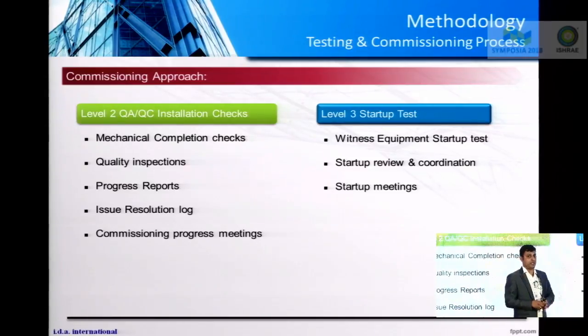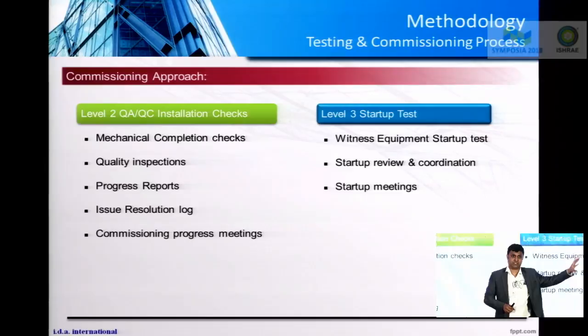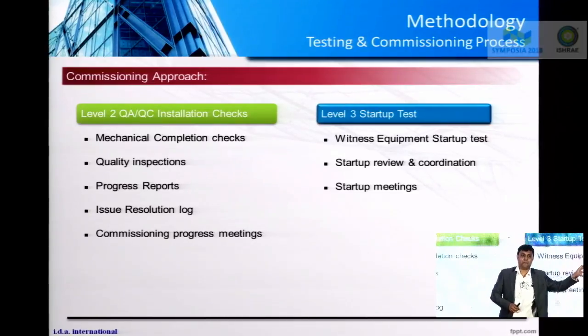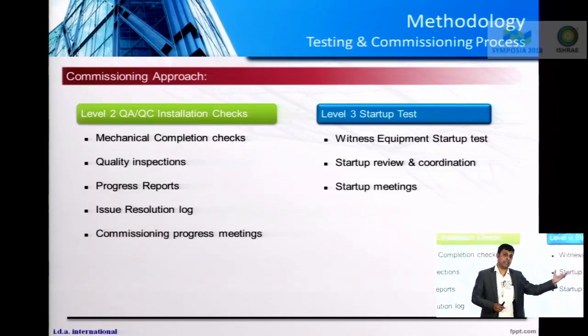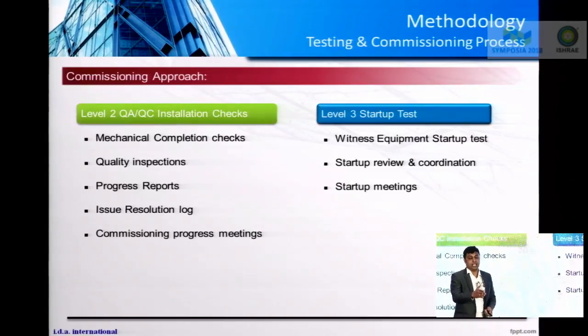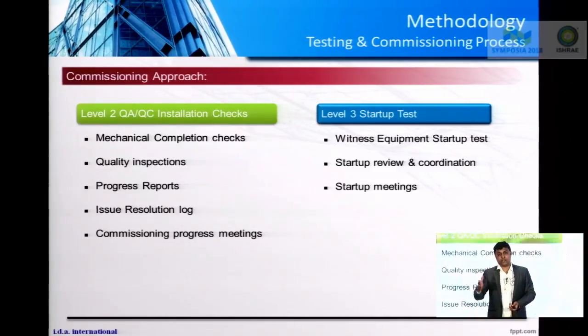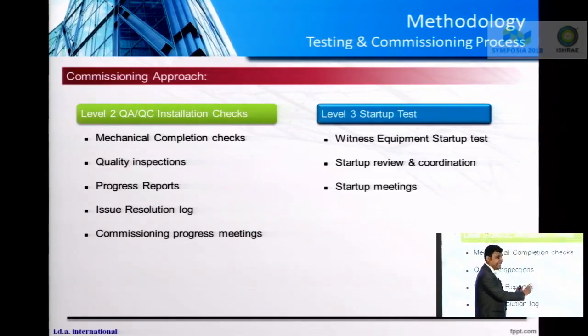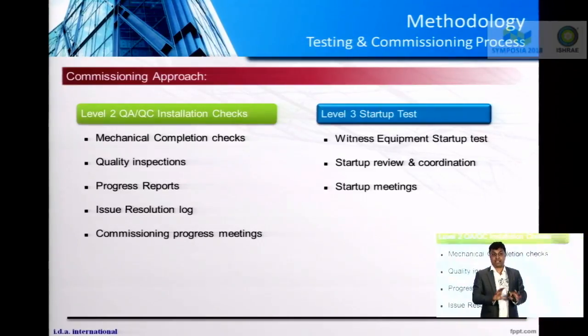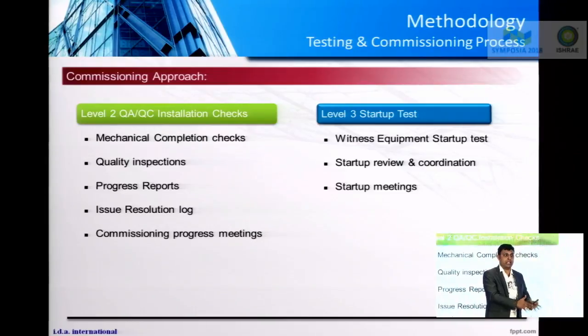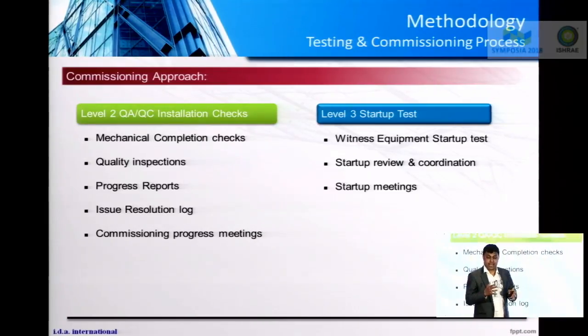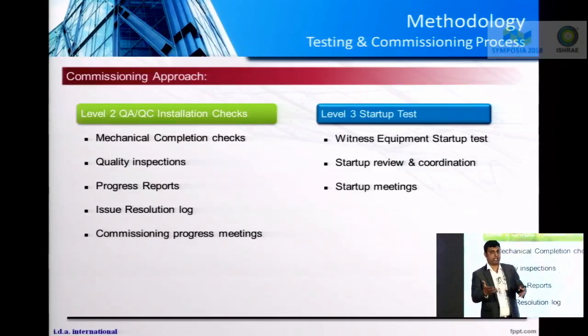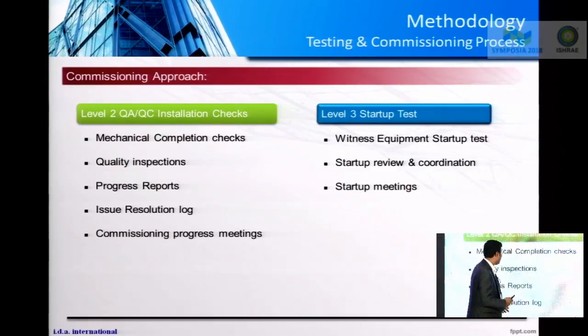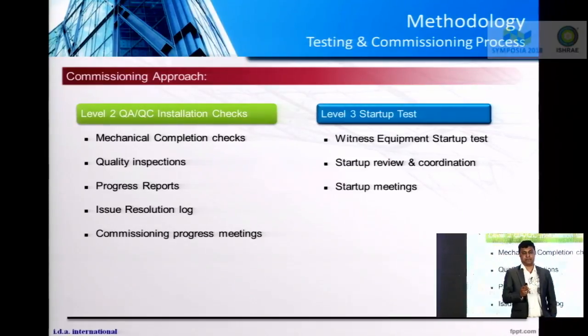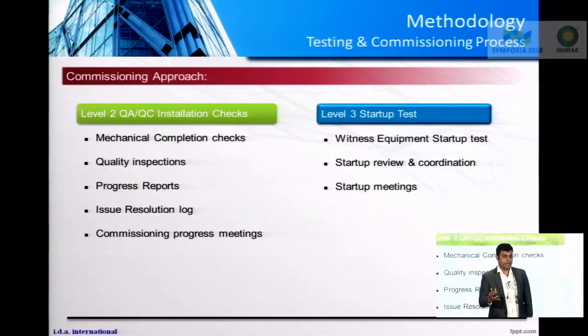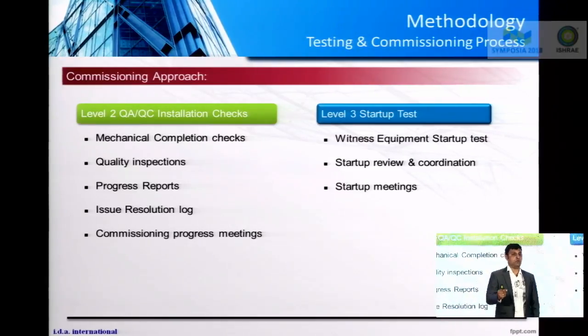Now, think of a scenario where you have spent so much time and money to do a factory acceptance test of a certain equipment, and some other equipment gets delivered on site. It would be disastrous because you have spent so much money and time, and you don't want that to happen, right? A proper quality inspection and checks would ensure that such issues don't arise. You have the equipment placed at the right location, the right equipments are delivered on site, and we have a continuous check on the quality of construction. The next step is level 3, which is startup test. The moment you are satisfied with the installations, it is time to energize an equipment.